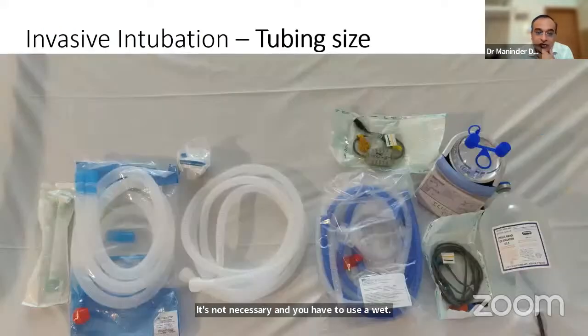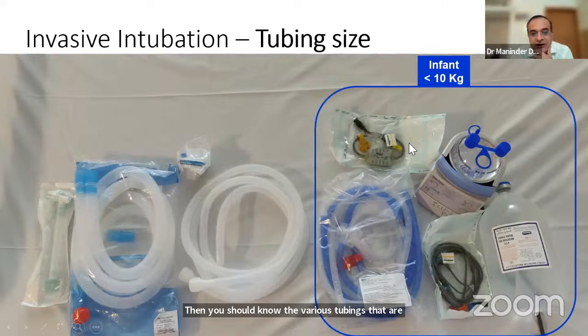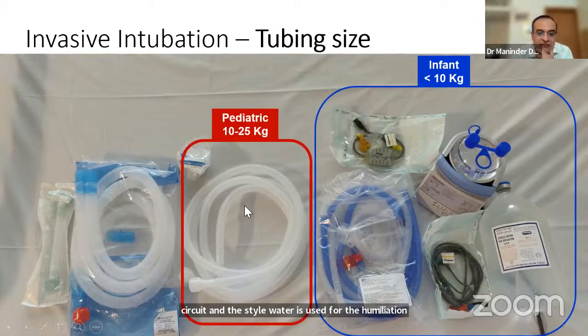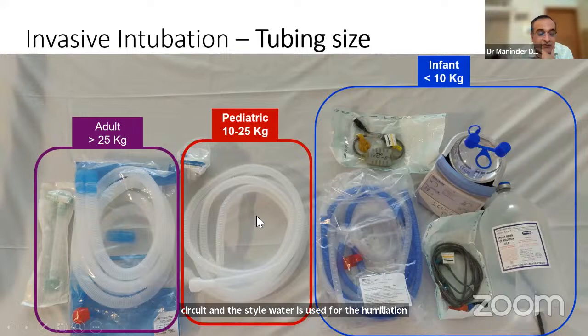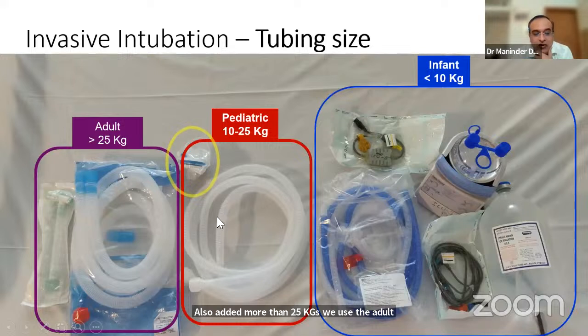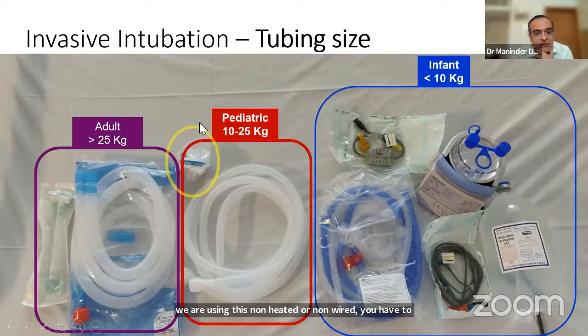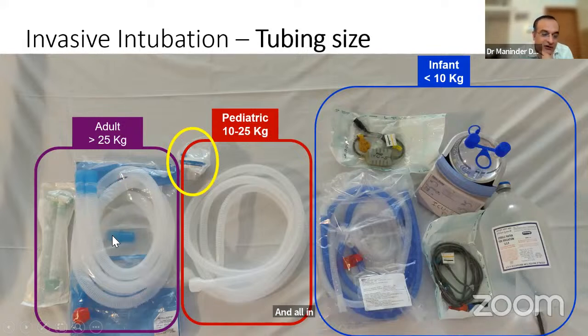You should also know the various tubings available. If it's less than 10 kg in our unit, we always use a wet humidifier with a double heated circuit, and sterile water is used for humidification. If it's 10 to 25 kg, we have pediatric tubings and prefer to use HMEF. For adults more than 25 kg, we use adult tubings. Remember, once you're using non-heated or non-wired tubings, you have to use an HMEF filter, otherwise the patient will get cold, non-humidified air, which causes more lung injury. In adults too, double heated or double wired circuits are available.